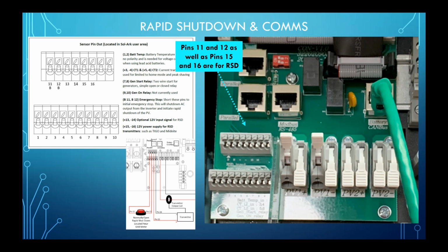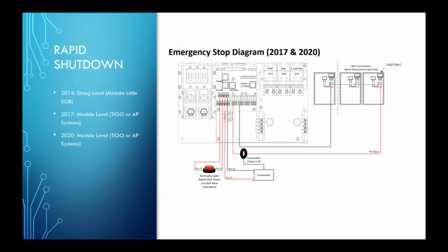So again, the total solution of rapid shutdown is a combination of third-party devices that are going to be used out on the array, and then integration back into the Sol-Ark that's going to bring those signals back in and integrate with it. This is a quick wiring diagram example of that. Let me move that down here. As you can see out here on the arrays over on the right side, you have the Tigo TS4s that are mounted out on the array. You've got your inputs coming in here. Pins 11 and 12 are the normally open rapid shutdown relay. Pins 15 and 16 run the power to the transmitter. And the total solution here is manifested by that combination of third-party devices and integration in the Sol-Ark itself.